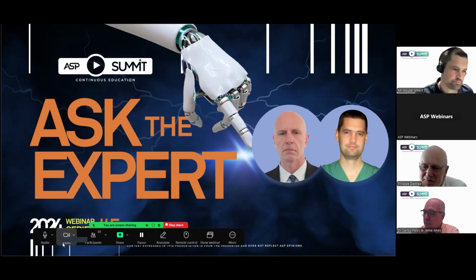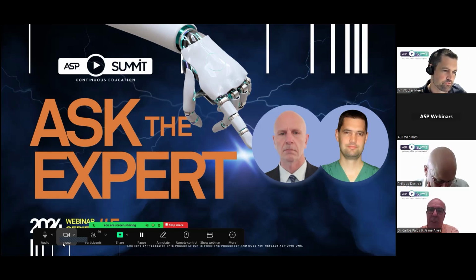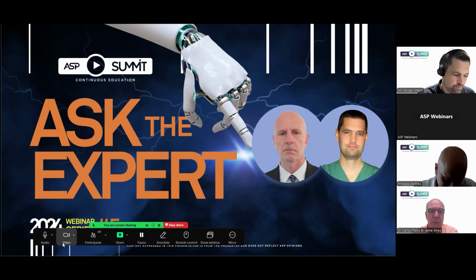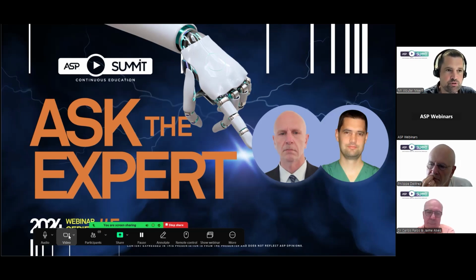And Wouter, well, how do we make sure that an MD is compatible with the sterilizer that you use? For medical devices, it's really important that if it's in the IFU, literally, it's the most easy way. But I think for a lot of devices that are not validated by the manufacturers already for hydrogen peroxide sterilization processes, you have to have a really close connection with your medical device and sterilizer manufacturer, and periodically, if you have lists, check them with them, and they will help you to make the connection between the medical device manufacturer and the sterilizer manufacturer to make sure that your device is compatible, that you assure sterility and you assure that your device will keep working in a correct way.